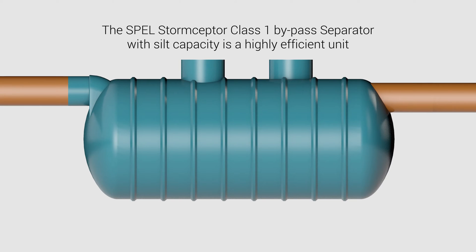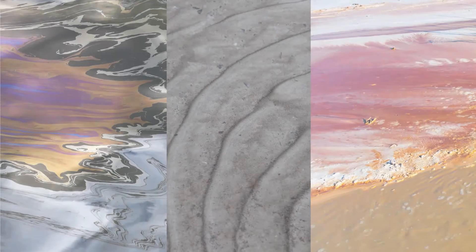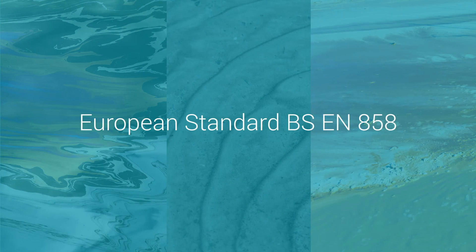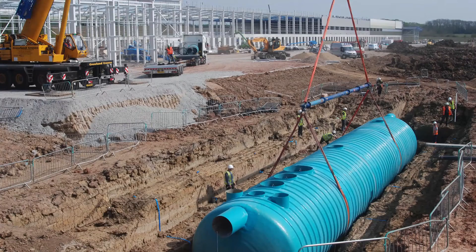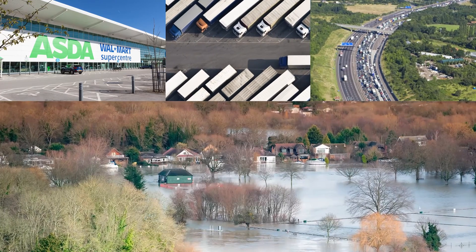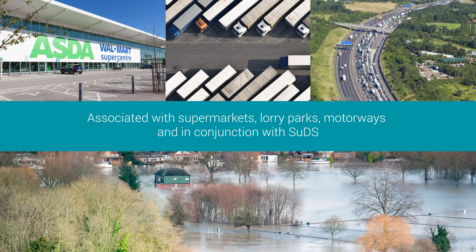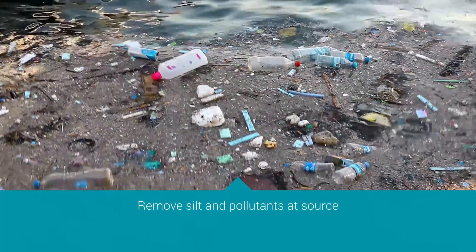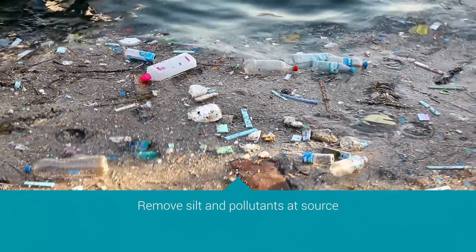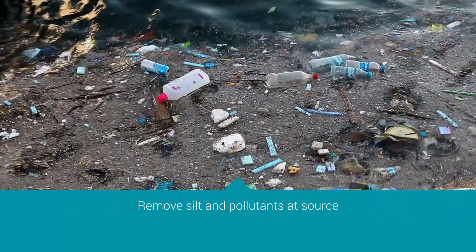The SPEL Stormceptor Class 1 Bypass Separator with silt capacity is a highly efficient unit for removing hydrocarbons, fuel and oil, silt and heavy metals as sediment bound. They're compliant with European Standard BSEN 858. They're used extensively for larger catchment areas associated with supermarkets, lorry parks, motorways and in conjunction with sustainable drainage systems, or as they're termed, SUDS. It is an important element in any SUDS treatment train to remove silt and pollutants at source rather than blocking up attenuation systems or downstream ponds that are difficult to desludge.